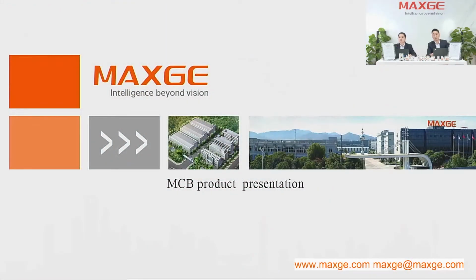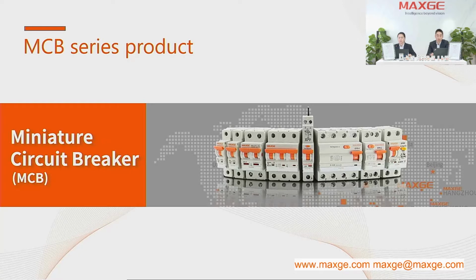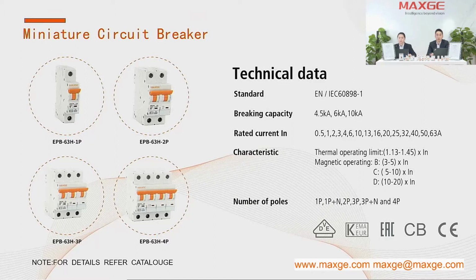Okay, now let me introduce our most popular series, Alpha Series MCB. Our Alpha Series, named EPB-63, is in compliance with IEC 60898-1 standard. We have 4.5, 6, 10 kA for breaking capacity, and for some countries, they also need the lower breaking capacity with 3 kA. Our MCB's rated current is from 0.5 ampere to 63 ampere, and it has 1 pole to 4 pole with BCDQ. We have already gotten the VDE, KEMA, CE, CB certificates.